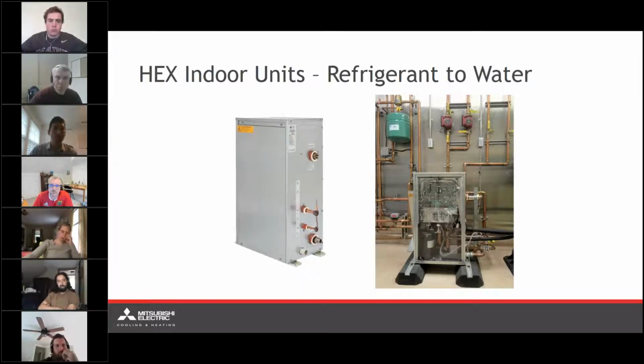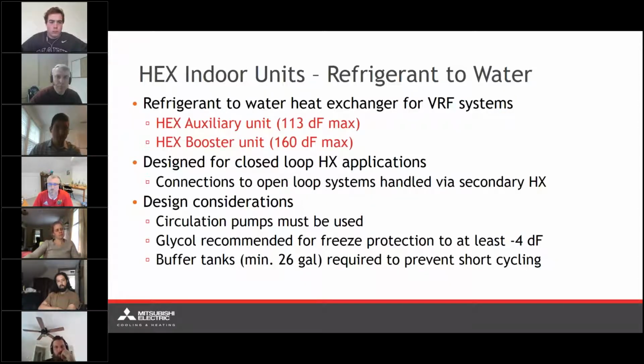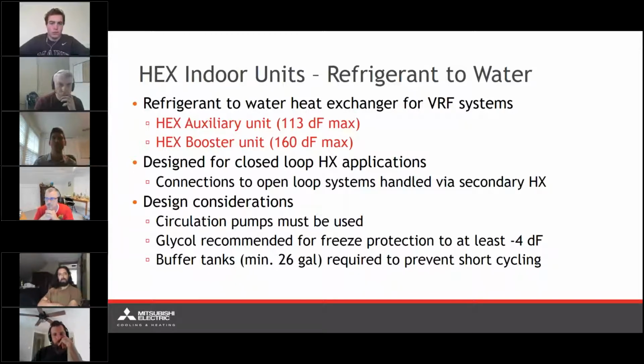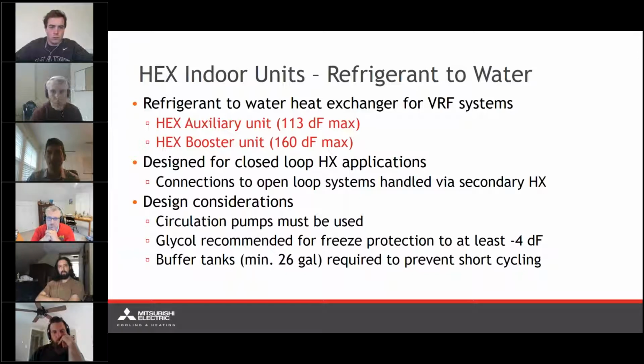All right. When we're talking about our HEX indoor units, we're going to be talking about one of two different series. We have our HEX auxiliary units, which are capable of heating water to 113 degrees, and the booster units, which can boost even higher with that independent compressor up to 160 degrees. Both the HEX and the booster unit are designed for closed-loop heat exchange applications. Connections to any other open-loop systems, such as domestic water, need to be handled via a secondary heat exchanger. We can't just have fresh potable water go through these and expect to be able to drink the water. These are for closed loop systems only.